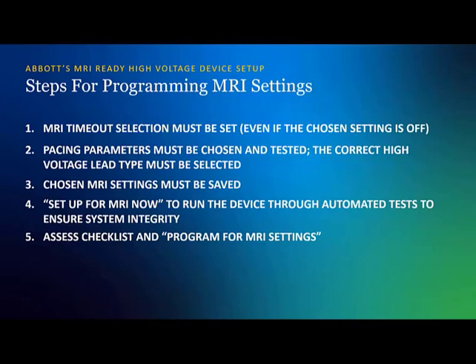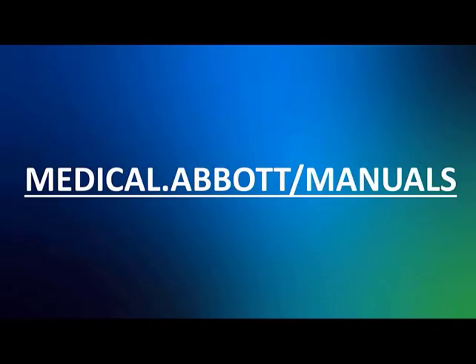It is important to print the MRI report for the MR technologist or radiology technician before ending session with the device. Following the scan, the device should be interrogated immediately to disable MRI settings and revert back to permanently programmed settings, including enabling tachycardia therapy. For further information on MRI safety, please refer to the MRI Ready Systems Manual available on medical.abbott/manuals.